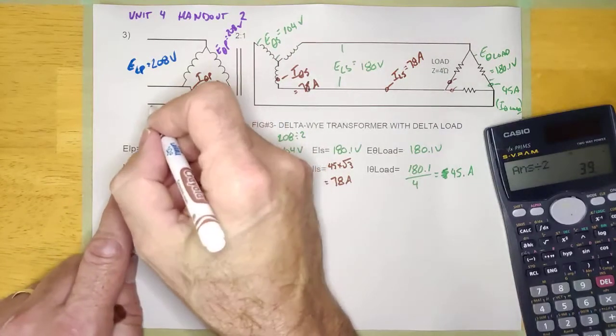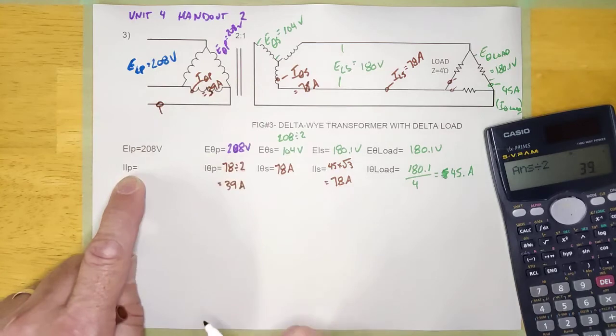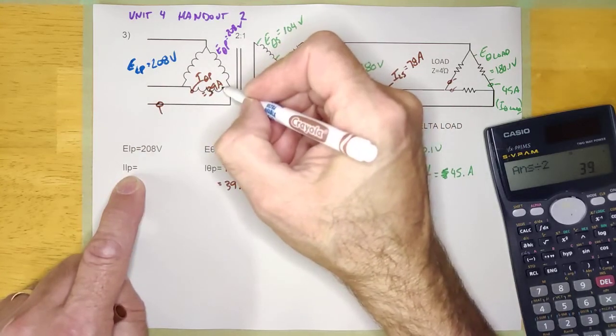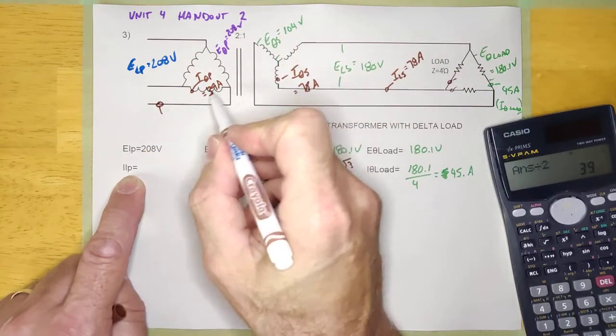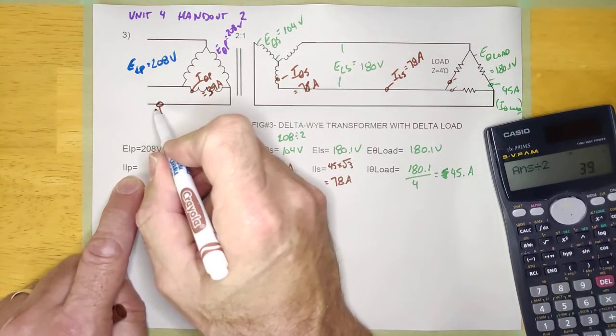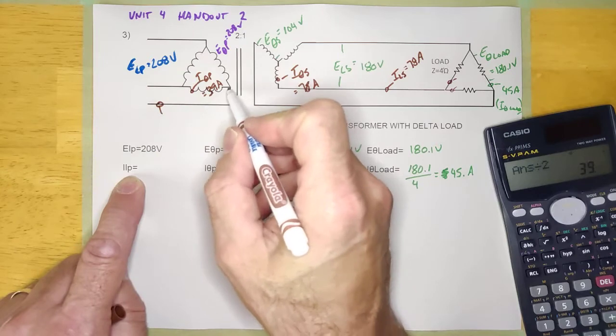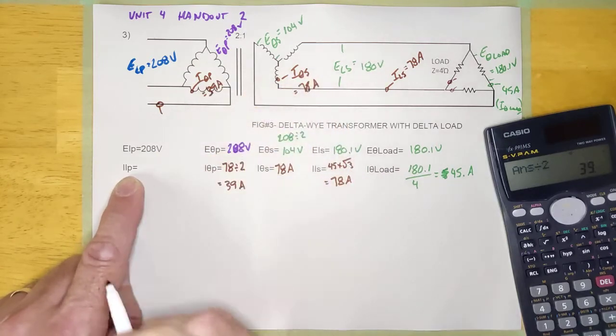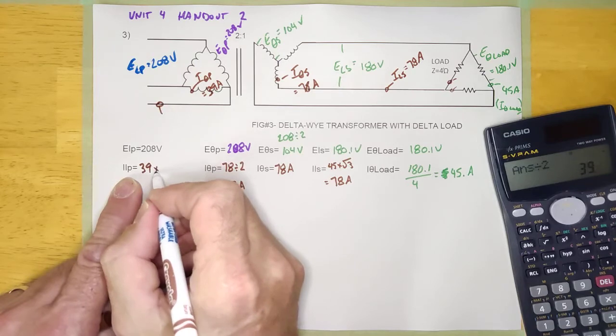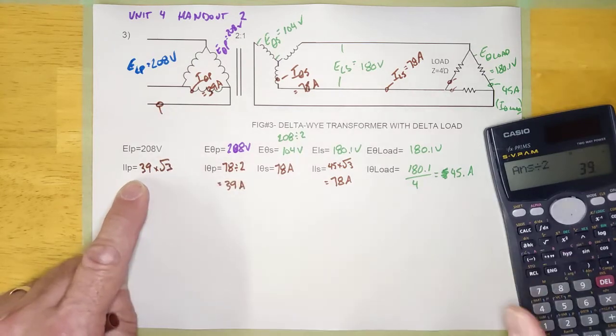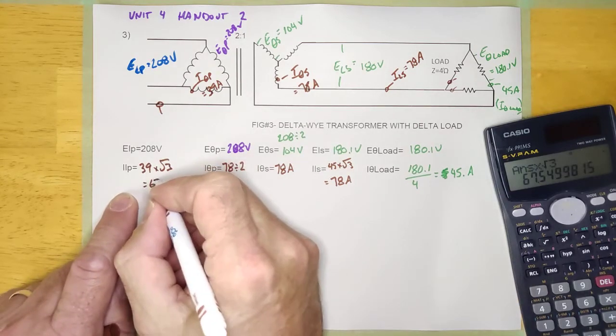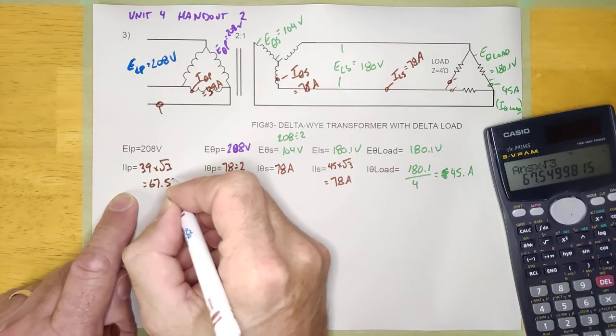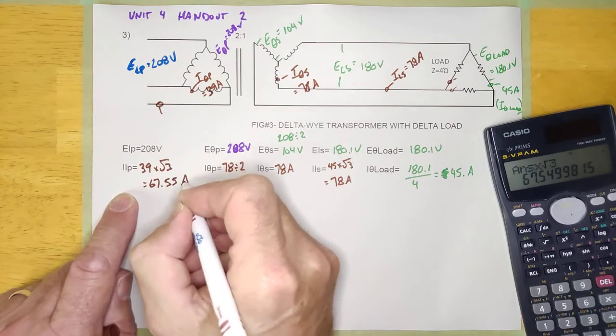Last one — I-line primary, which would be the current right here. I have 39 amps here and 39 amps here. That current is going to feed both of those, so it's going to be more — I'm going to multiply. 39 times root 3 equals 67.5 amps.